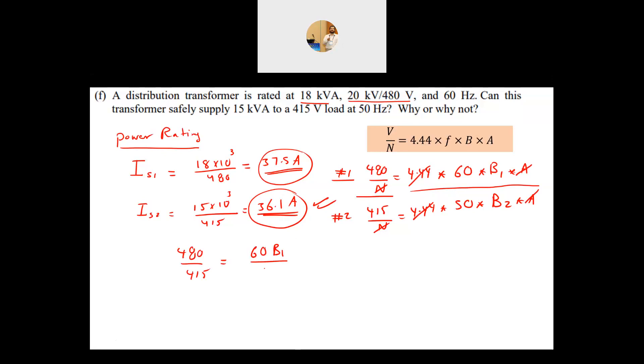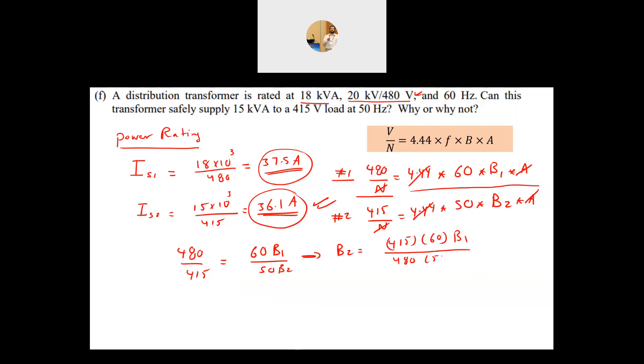The transformer was designed to operate at B1, so it can handle B1. The question is whether it can handle B2. Solving the equation: B2 = (415 × 60 × B1) / (480 × 50), which gives B2 = 1.037 × B1. This means the second operating condition produces a higher flux than the original design.